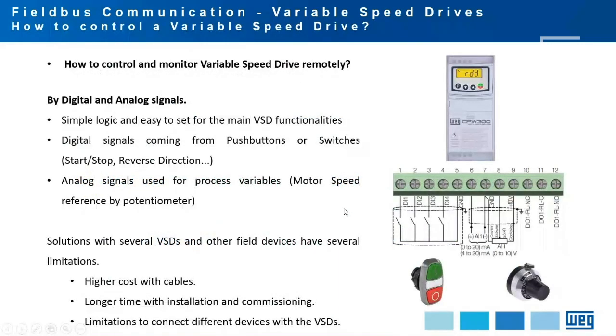To start, it's important to understand how we can control a variable speed drive remotely. Probably you think about digital and analog signals, as this is the easy way — a simple logic easy to set with most variable speed drives, using simple devices like push buttons, switches, and analog signals such as a potentiometer installed close to the drive. However, with digital and analog signals we don't have access to all parameter settings, and there are several limitations when multiple variable speed drives are installed in a cabinet, machine, or process.